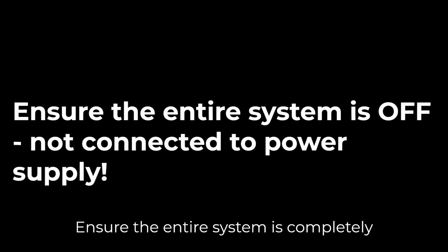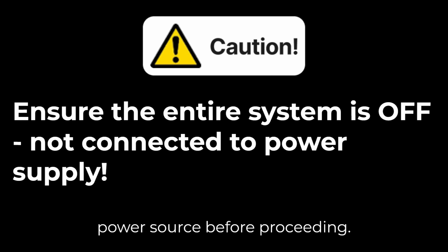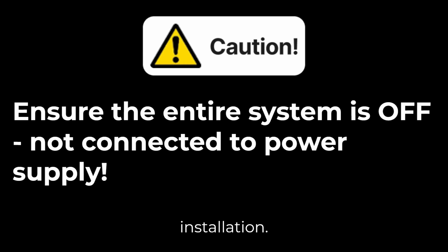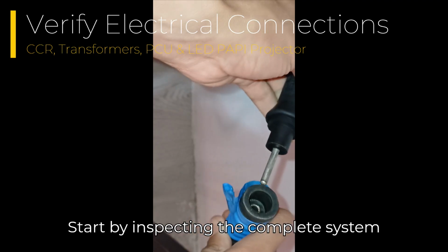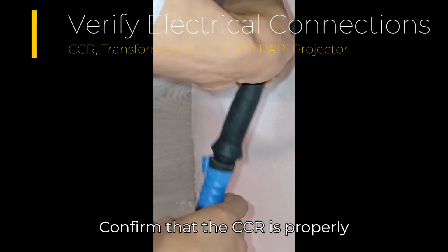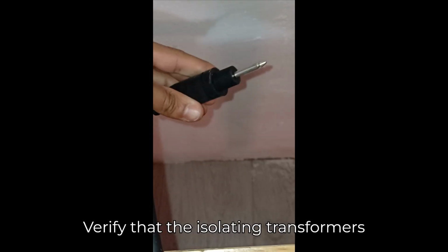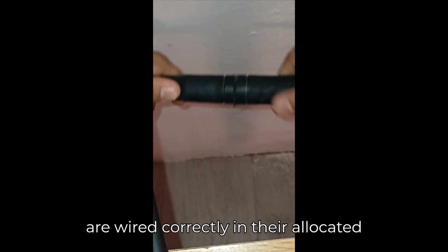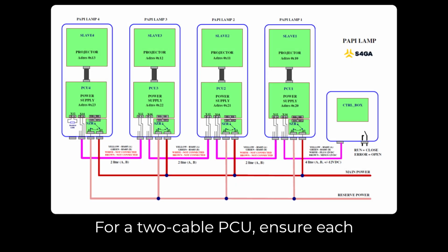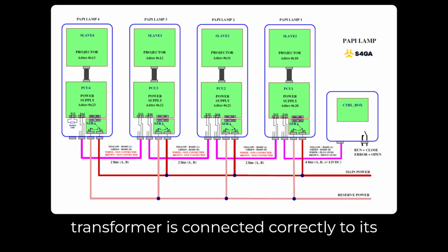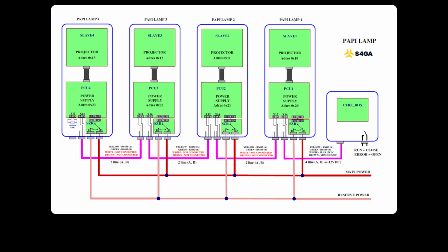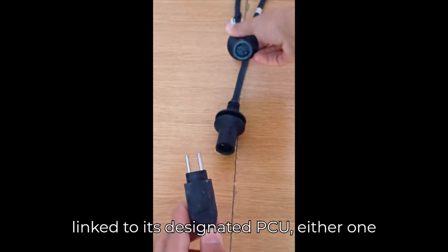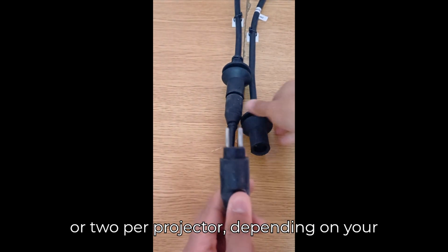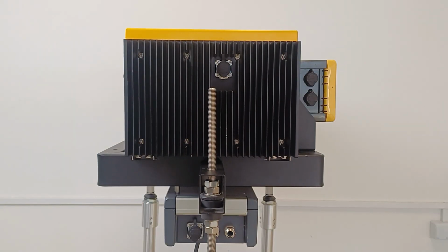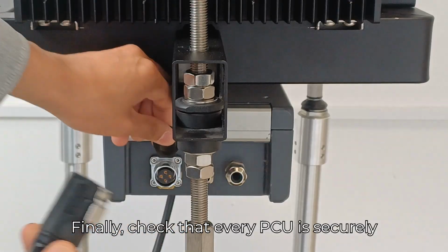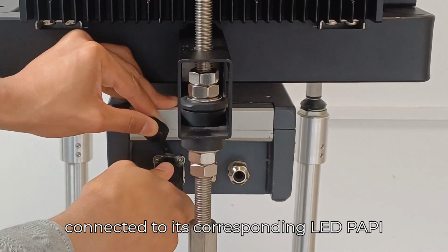Ensure the entire system is completely powered down and disconnected from any power source before proceeding. This is essential for safe inspection and installation. Start by inspecting the complete system wiring. Confirm that the CCR is properly connected to the main power source. Verify that the isolating transformers are wired correctly in their allocated circuits. For a 2-cable PCU, ensure each transformer is connected correctly to its allocated primary or secondary circuit. Ensure that each transformer is correctly linked to its designated PCU, either 1 or 2 per projector depending on your setup. Finally, check that every PCU is securely connected to its corresponding LED PAPI projector.